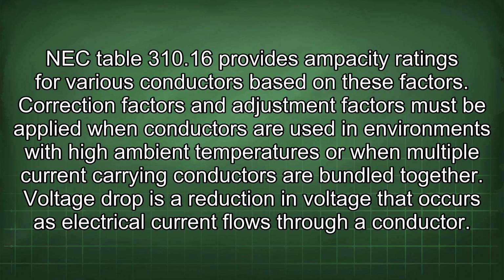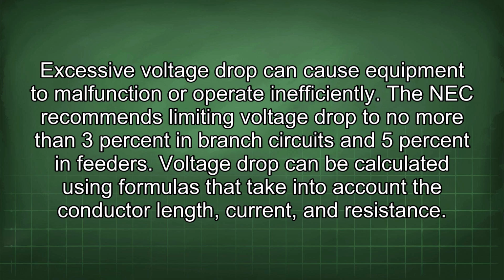Voltage drop is a reduction in voltage that occurs as electrical current flows through a conductor. Excessive voltage drop can cause equipment to malfunction or operate inefficiently. The NEC recommends limiting voltage drop to no more than 3% in branch circuits and 5% in feeders. Voltage drop can be calculated using formulas that take into account the conductor length, current, and resistance.